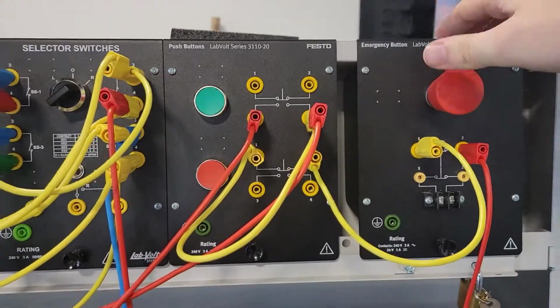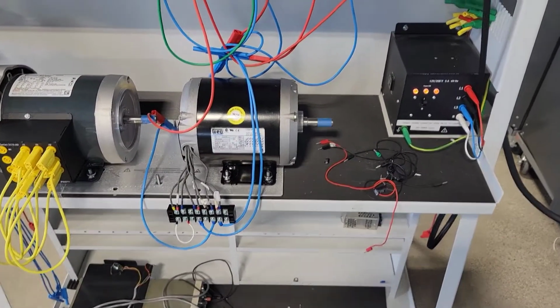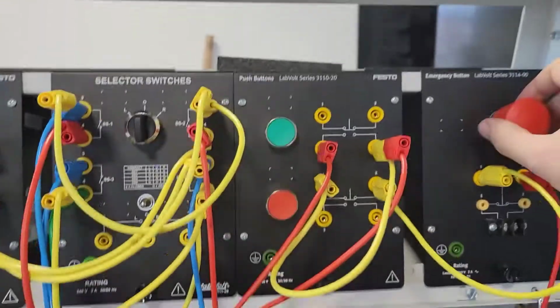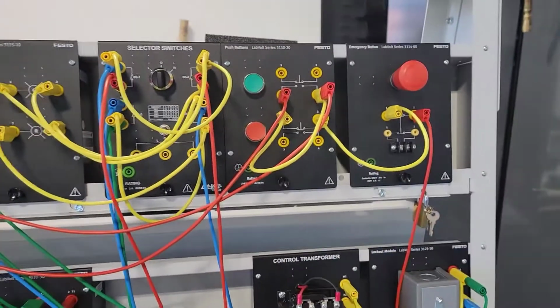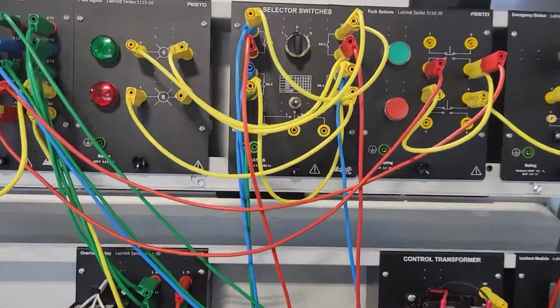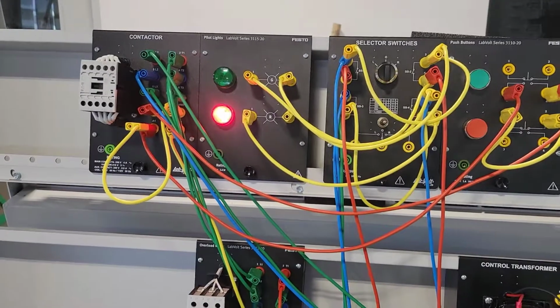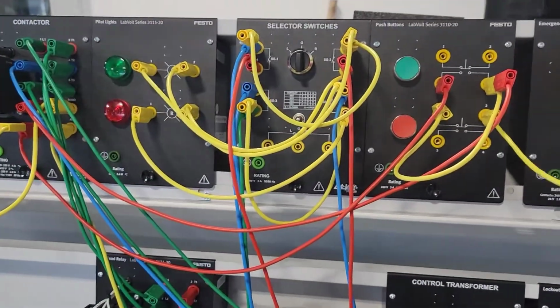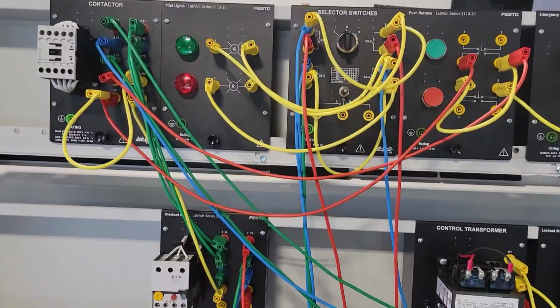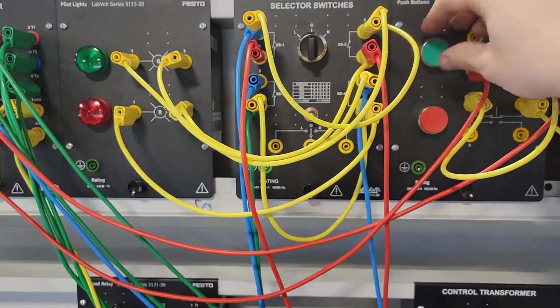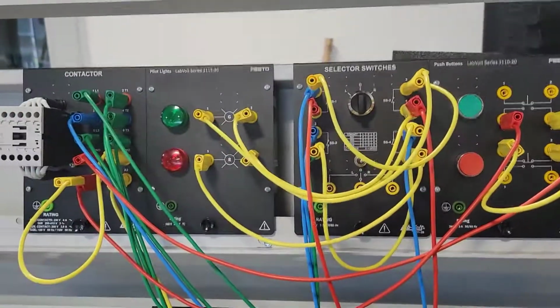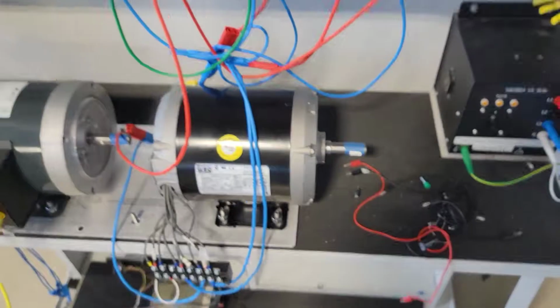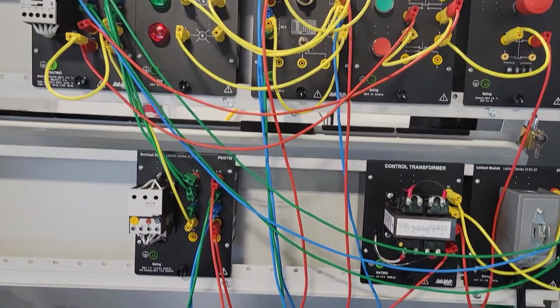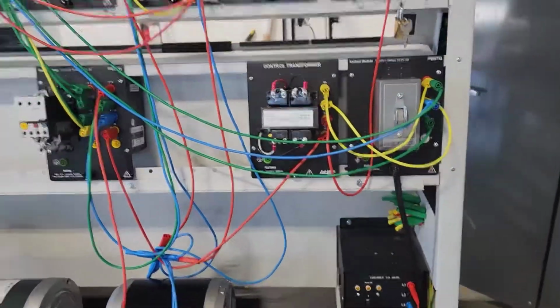And then the difference between the two-wire and a three-wire is that, unlike the two-wire, when the e-stop is turned back on or pulled out, the circuit does not turn back on and needs to be manually turned back on. So you can see that with the e-stop. E-stop is back out. The circuit is indicated to be off by the red light. It's back on. E-stop. It's off again. So that is the benefit of the three-wire, at least in safety regard, and that is the lab.